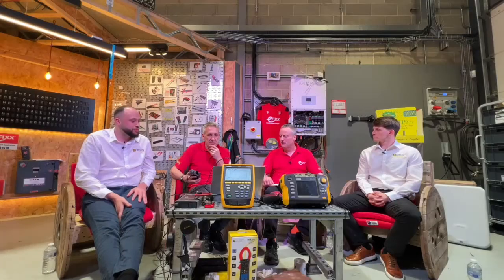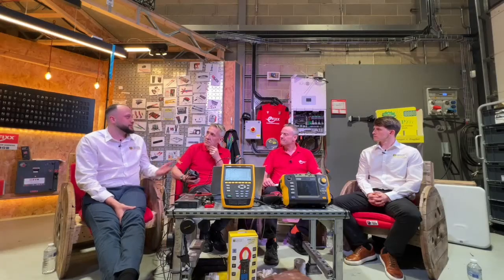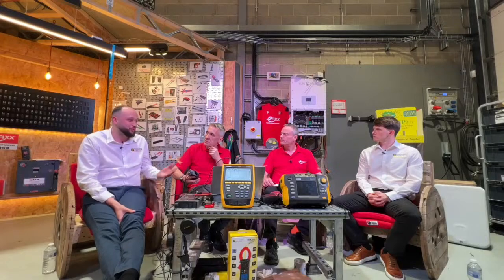Okay, so we're not calling that entry level - that's probably your first dive into taking ownership of understanding what's happening in the installation. I love the maximum demand. If you've done an EV install and you want to go back to the DNO for over voltage issues that aren't at your fault, and you don't want to absorb that cost, you can potentially get the DNO in some instances to tap down the transformer.